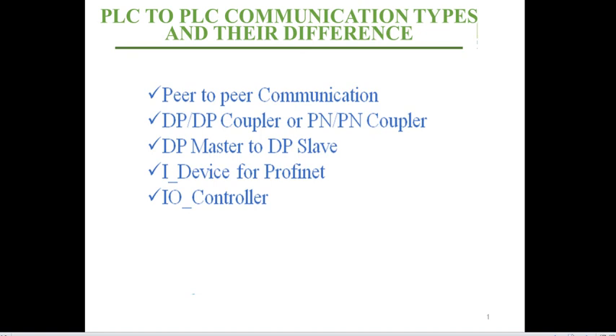The fourth type is where one PLC acts as a controller and the other acts as a device — this is for Profinet. The fifth is not PLC-to-PLC communication; it's about connecting an IO module to a PLC where the PLC doesn't have a Profinet port but the IO module does, so we use a communication processor that acts as an IO controller.